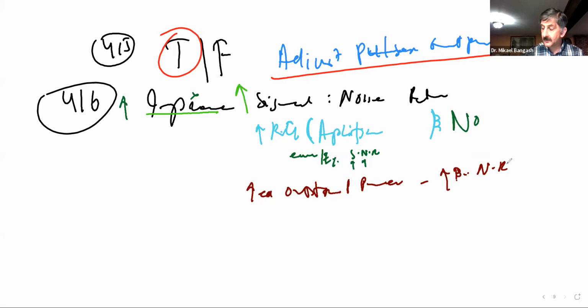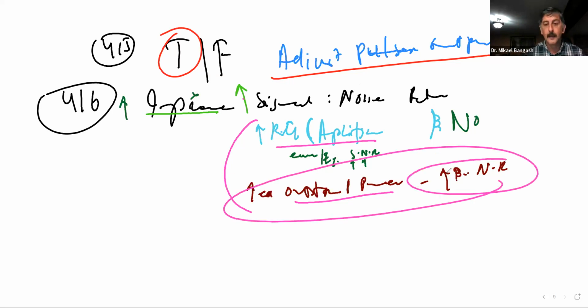Increase time gain compensation. Now, time gain compensation has no relation to your signal to noise ratio, so that is out. Dynamic range also has nothing to do with the signal to noise ratio. The only two factors that influence your signal to noise ratio are the amplification and the power output. More signal, less noise, where do we get that? By increasing the power output.